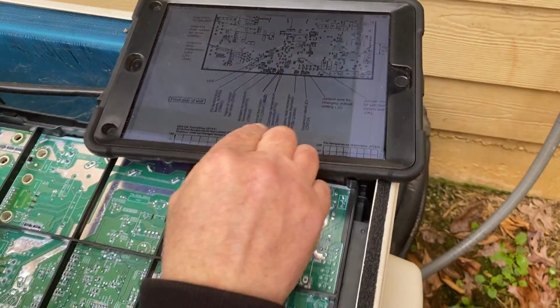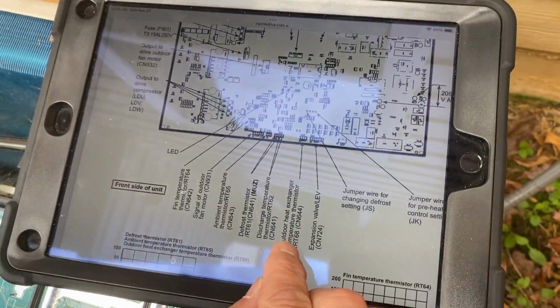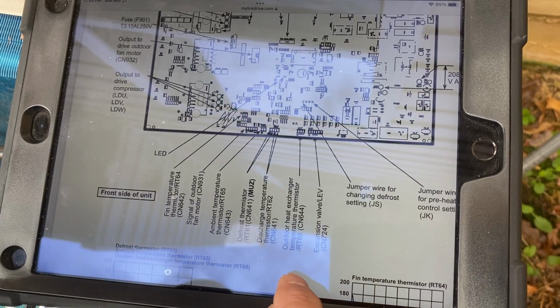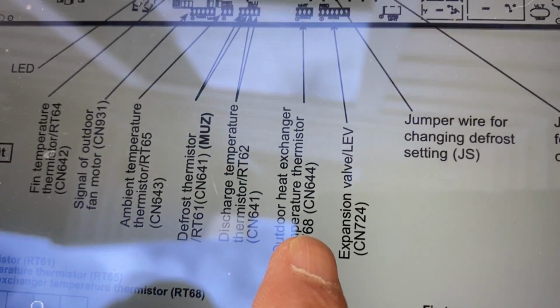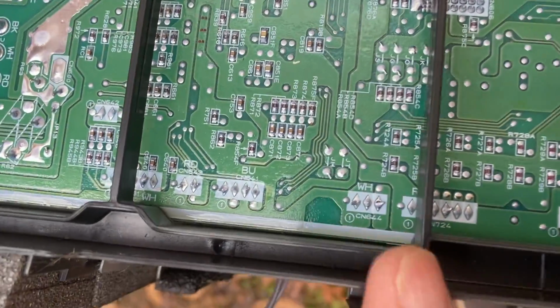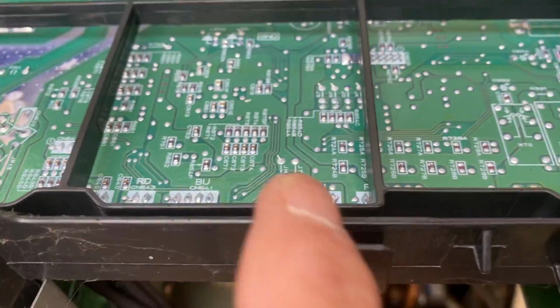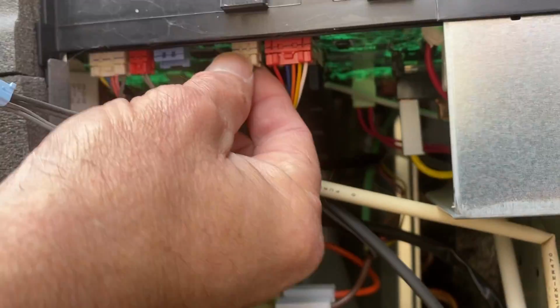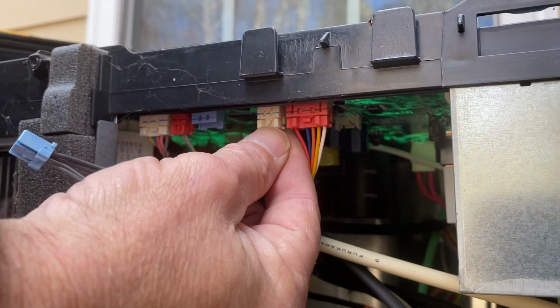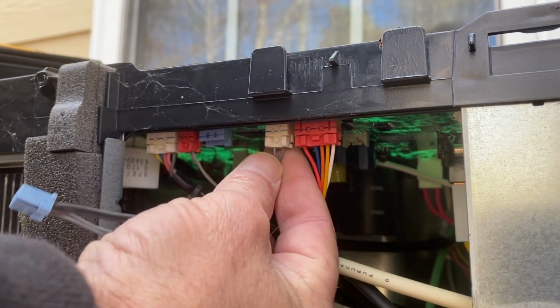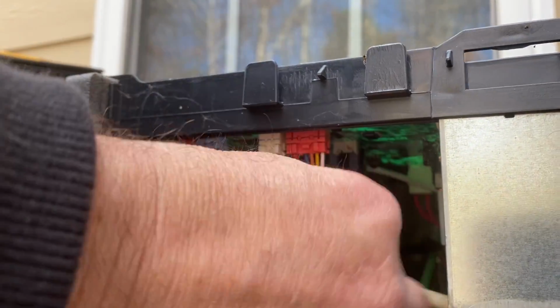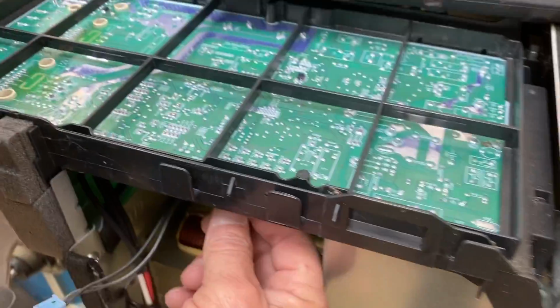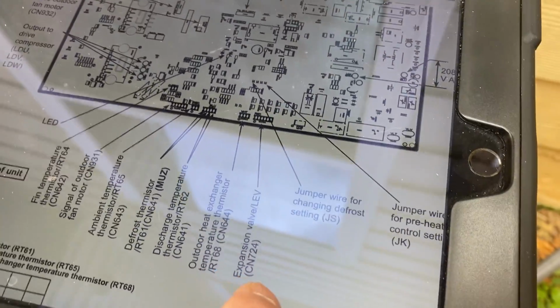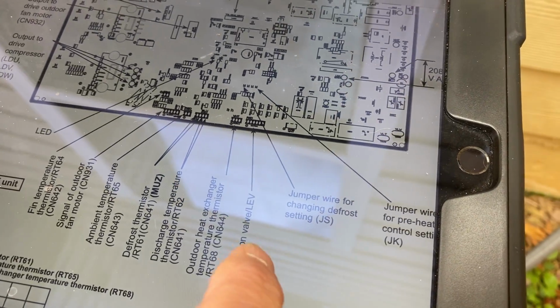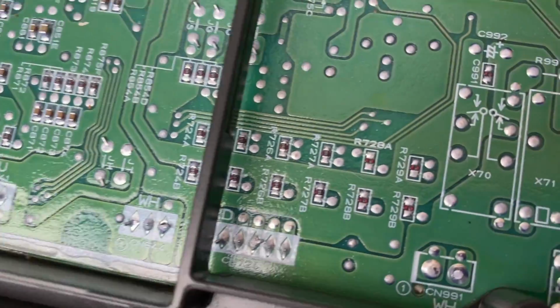And of course, the outdoor heat exchanger temperature thermistor is CN644. Find it right here, CN644. We go directly underneath it, which would be this white one right there. That would be your outdoor coil thermistor. And this right here, you want to know what that one is, that would be your LEV, which would be CN724. So that would be it.